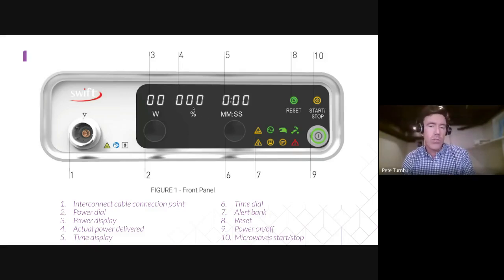For most of your doses, it'll show what percentage was delivered after each dose of energy. Most of the time it'll be in the high 80s or low 90s, which is great. Everything above 80% is within spec of the treatment. If it goes below 80, that's where the system says, nope, I'm not happy with that, and turns the dose off. So that's where you just hit reset and keep going. Does that make sense? Yes, that makes sense. Perfect. It won't happen that often, but you'll see it happen every now and then.